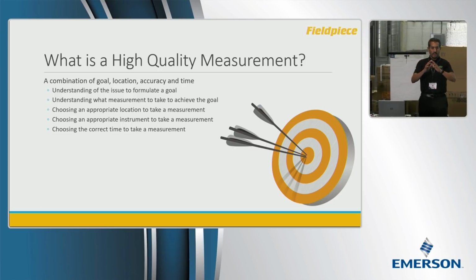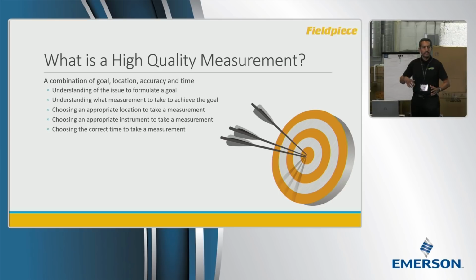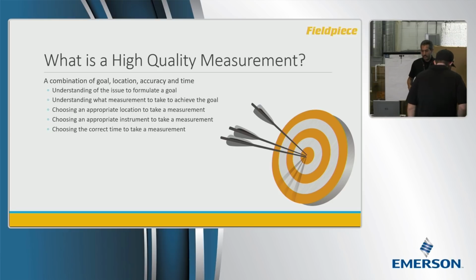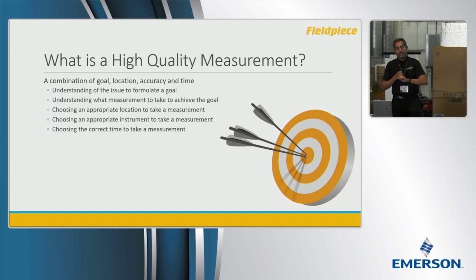You guys take measurements all the time on your jobs, constantly, dozens of times a day. And it's extremely important that you take good, high-quality measurements. So what does that mean? Number one, you kind of have to have an understanding of the issue that you're looking for in order to take a high-quality measurement. You got to know, am I trying to find an airflow issue or a charge issue? Because if I'm looking for an airflow issue, I'm not going to be measuring pressures and temperatures at the outdoor unit. It seems obvious, but there's a process to this.